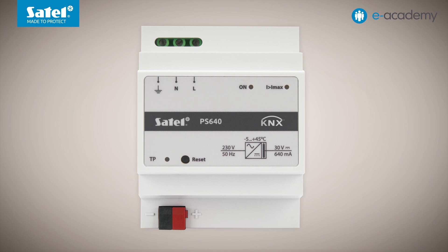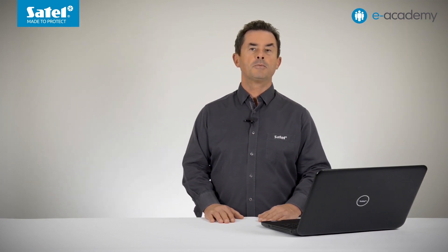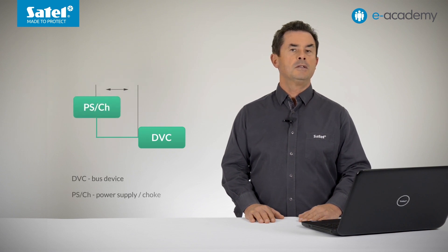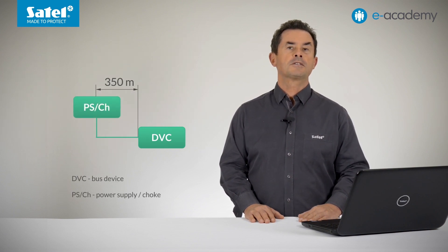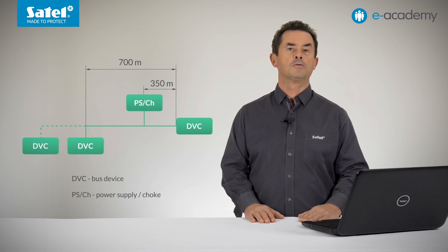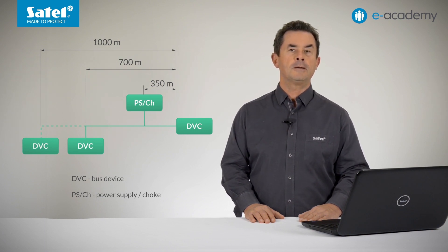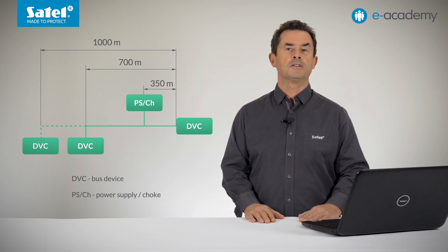When necessary, it is possible to connect more power supplies to the line, although this is subject to certain restrictions as well as manufacturer's recommendations. It is worth adding that, in order for the smooth operation of the system, the length of the cable between a single bus device and the power supply must not exceed 350 m. The cable length between two bus devices must not be longer than 700 m. As for the maximum length of a single line, this can be up to 1,000 m. The minimum distance between two power supply units working in one line should be 200 m, unless otherwise specified by the manufacturer.